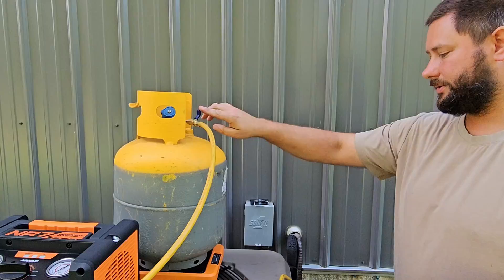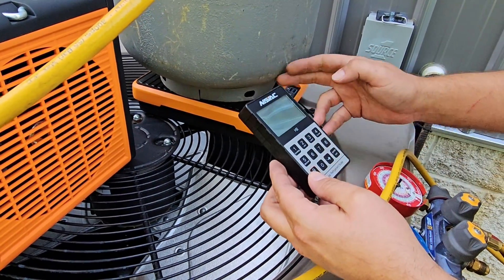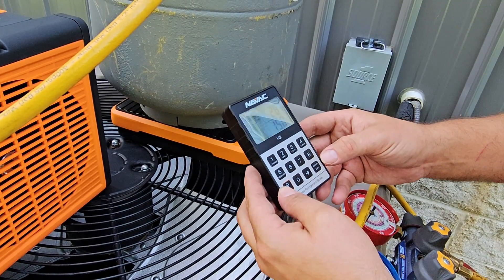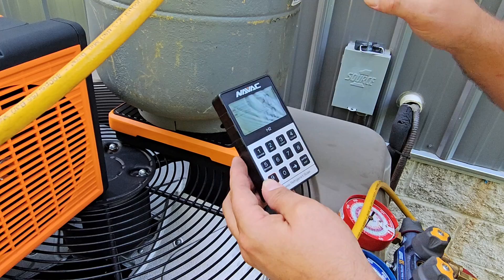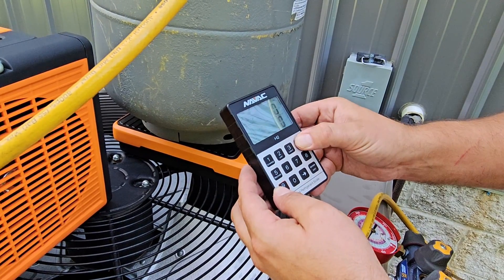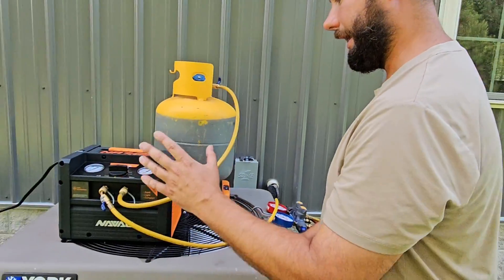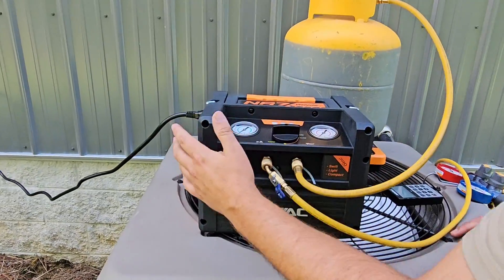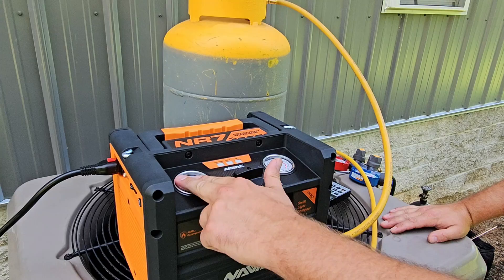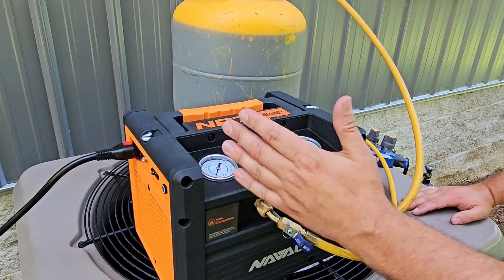We're going to go ahead and turn the power on to the NAVAC wireless scales because we want to weigh in the refrigerant. The tank weighs 28 pounds and 15 ounces — about 29 pounds — so we're going to clear it. You want to make sure you weigh the refrigerant going into the tank. Now let's turn the power on to the recovery machine. They have oil-filled gauges to reduce fluttering and vibration, which is nice. They have one knob to control how slow or how fast we recover, and they've got a purge setting for that dial.